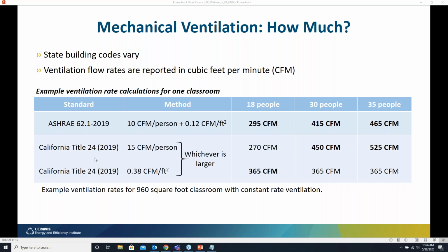California's Title 24 has slightly different requirements that result in larger amounts of ventilation, just slightly. And those are calculations that are based either per person or per floor area, and then you have to provide the amount that is larger. So in California, even if you have one person in that classroom, you need to provide 365 CFM, and then as you add people, the rate increases. But generally speaking, just to order of magnitude here, for a fully occupied classroom, we're talking in the realm of 450 to 500 CFM of ventilation for a classroom.